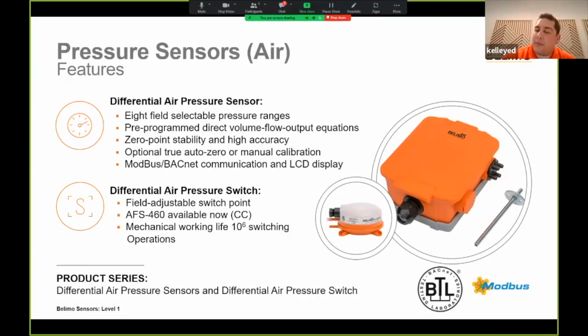We also offer pressure switches, which is the clamshell-looking device in the picture at the bottom. These are heavily used for filter monitoring. As a filter gets dirtier, you'll have a buildup of pressure upstream. Depending on that DP level, it will flip its switch and tell your BMS system when it's time to change the filter. Sometimes we see these run across fans as well. If there's an issue with a fan, you'll have either a drop or an increase in pressure. All of this just alerts the BMS, saying, hey, something's going on. Let's go out and check the device and see what's actually happening.